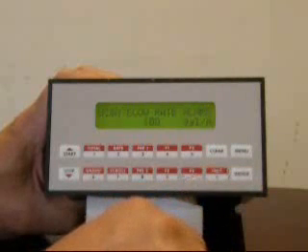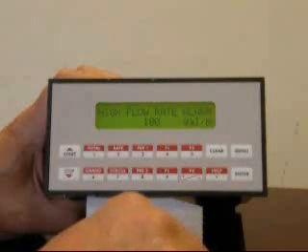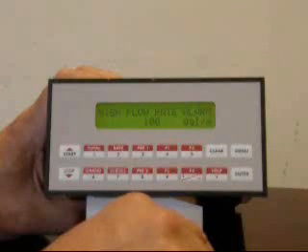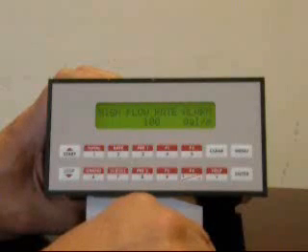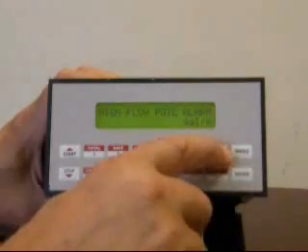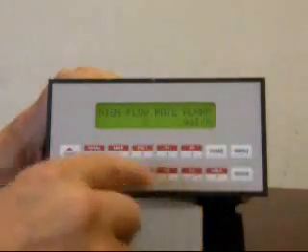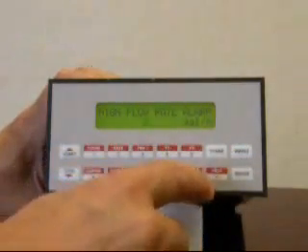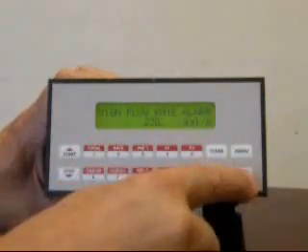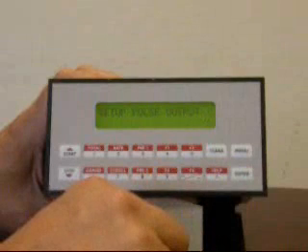In the case of the high flow rate alarm, we're going to change this number to enable no warnings unless the flow rate exceeds 220 gallons a minute. Again, to change a message, we just will hit clear, enter the new value of 220, and press enter. At this point, the entry selections for the flow input have been completed.